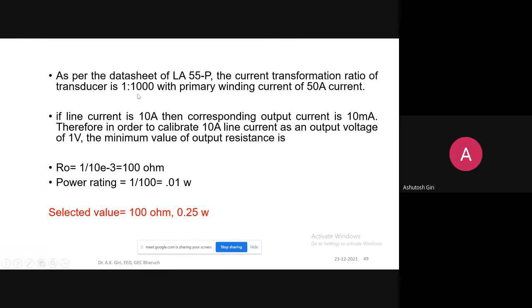Because the transformation ratio is 1000, suppose if 1000 ampere is flowing from the primary side, 1 ampere we will get at the secondary side. But although the transformation is like this, we cannot flow 1000 ampere from the transducer—the current limit of the transducer, the primary current, is limited to 50 ampere only.